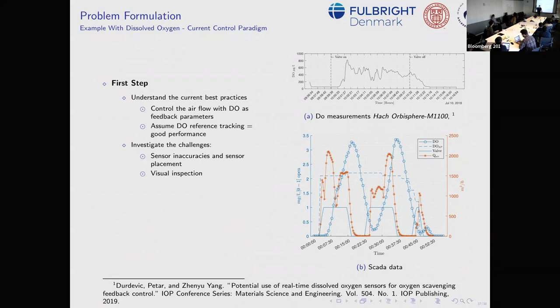The SCADA system has a biological model, something similar to a table lookup that looks at parameters and sets a set point — it's a supervisory cascaded controller, and then a P-controller controls the valve based on the set point. When it overshoots it simply switches off, then switches back on — that's why we have these strong cyclic behaviors. The control operates every two or four minutes, which is too slow for the oxygen dynamics.